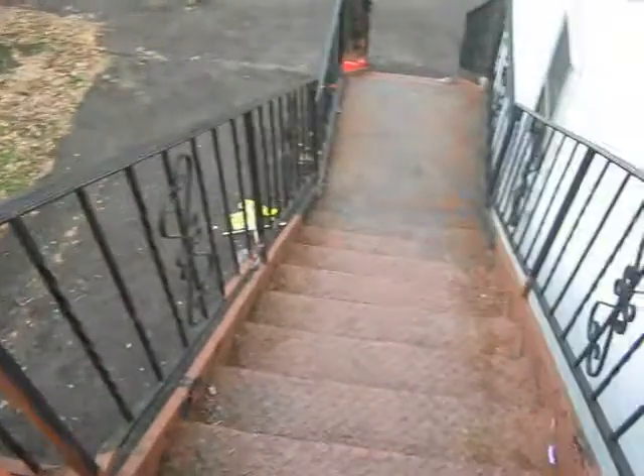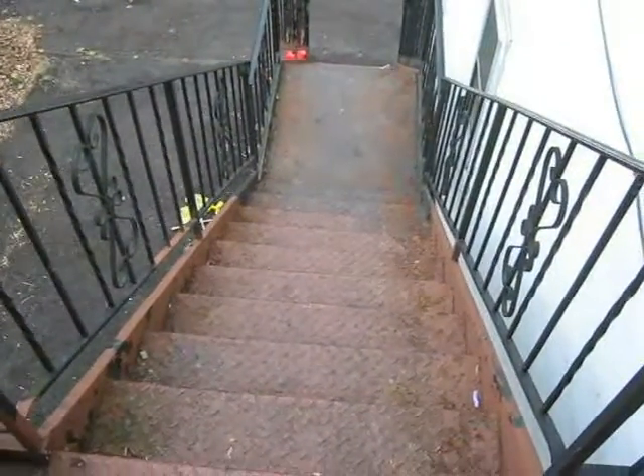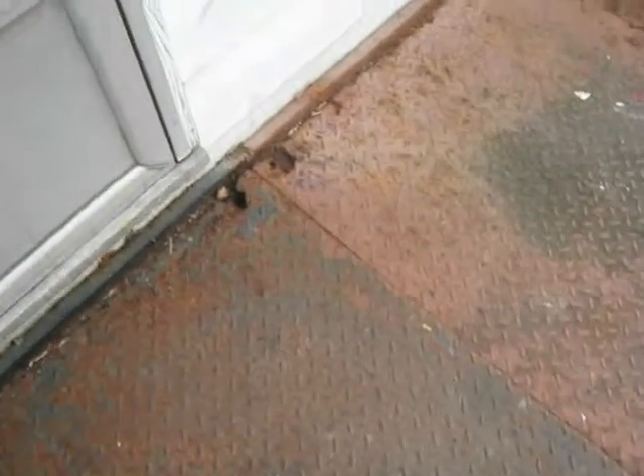We can spot repair this fire escape, but it's going to be quite extensive spot repairing and then proceed to a load test. Or we can fully refurbish this fire escape, provide other evidence of strength to the official, and avoid a load test. I believe this fire escape is at the point where the work needed is considered refurbishment, and that full refurbishment will forgo the load test because you've got quite a bit here that just needs work.